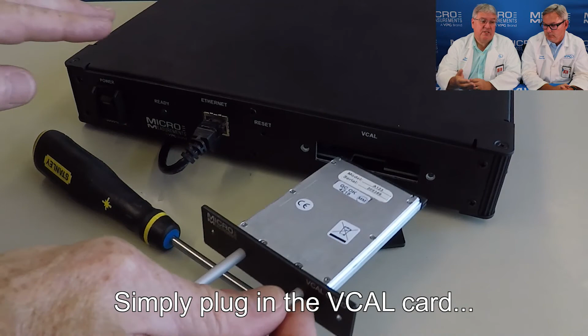The other thing that I wanted to show you is the next tab that says calibration. This is a system calibration. So what that means is that we wind up as an option with the 8000 and the 9000, but standard with the 7000 and 7100 is a VCal card. The VCal card is an NIST traceable device based on the resistance, in which you can send that in at your recalibration cycle, and then it gets provided for either the 8000 or any of the other data acquisition systems to do a system adjustment, not just a verification.